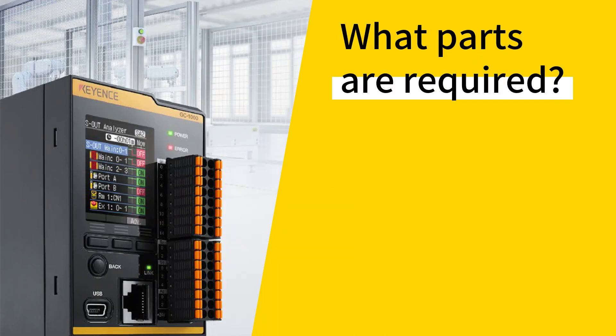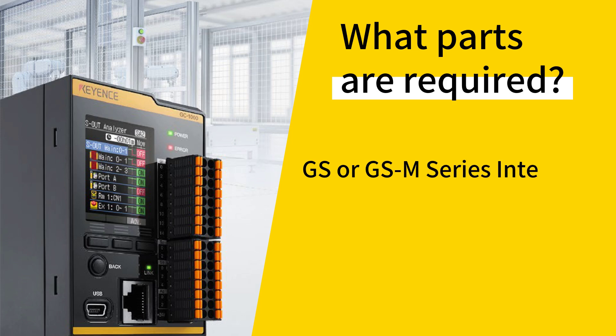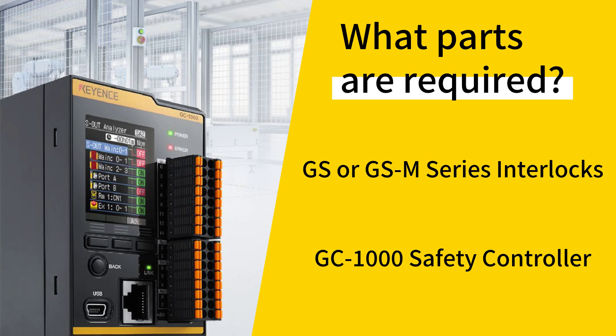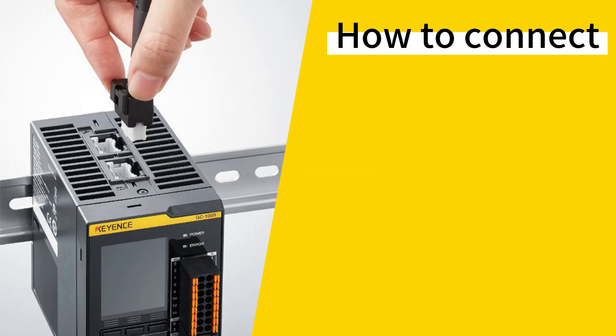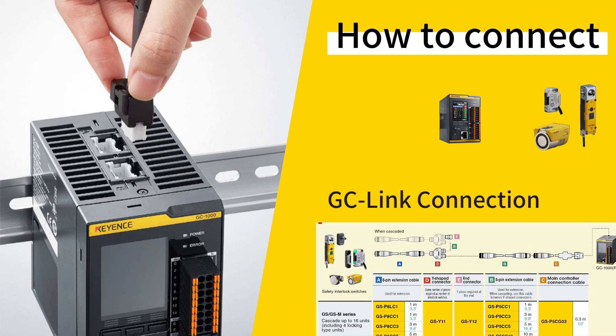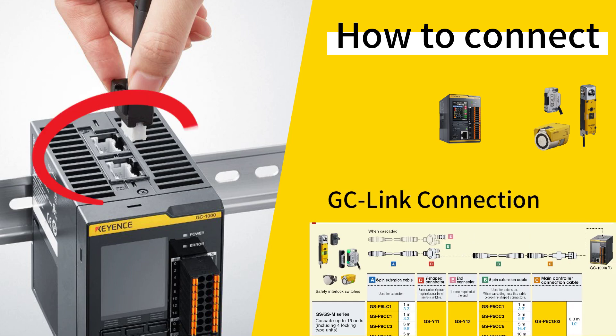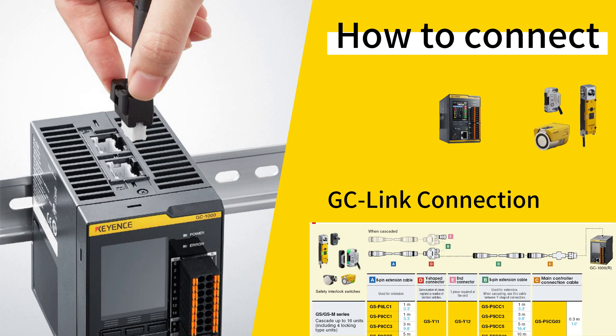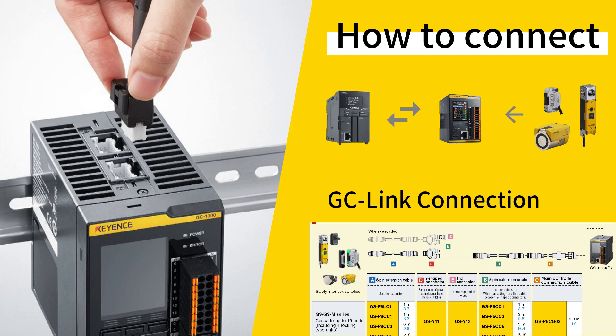If you want to see the door status of your GS or GS-M series interlocks in your PLC, you need to connect the interlocks to the GC1000 safety controller from Keyence. Specifically, you need to connect the interlocks to the GC1000 safety controller via one of the GCLink ports on top of the GC1000. This will allow the interlocks to communicate the lock or open status of each door, even if the interlocks are connected in series.